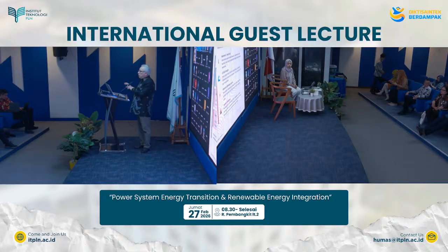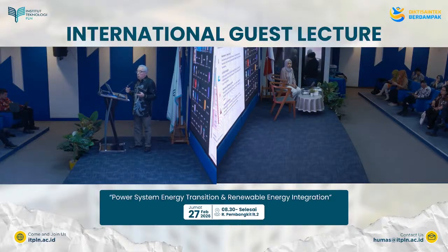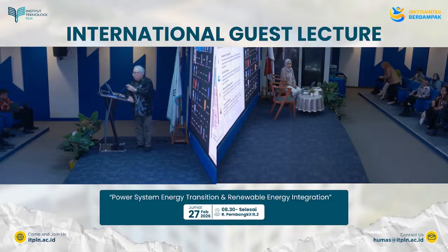Okay, not continue to operate. You are going to lose some load. You are going to lose generation. Your frequency will go down, but you can recover quickly, right? So that is a resilient system. If you can recover, you can absorb the shock and not have a total blackout, where all the system goes down. Okay, so that's a resilient system. A survivable system goes beyond n-1 and n-2. What you are trying to answer is, can the system survive the event and maintain frequency within safe limits throughout? Okay, so you have to have some of the system survive, not total blackout, not all of the system, so that you have a basis for full recovery. Okay.